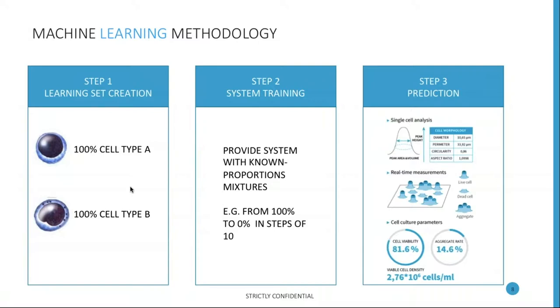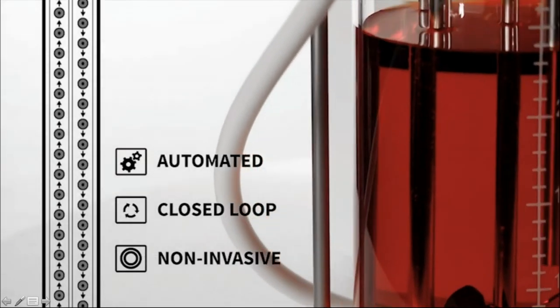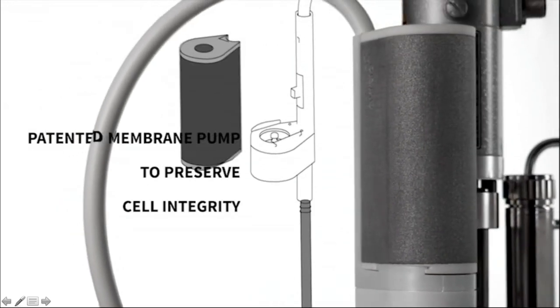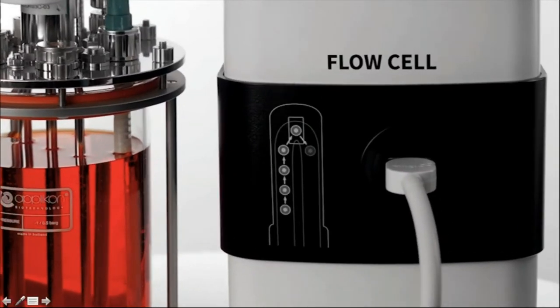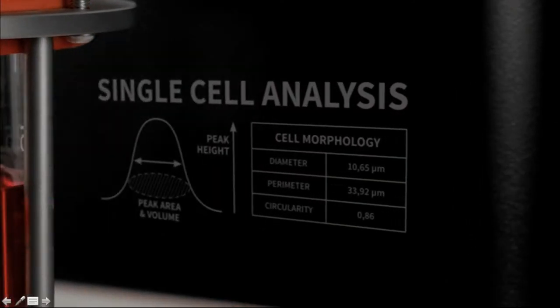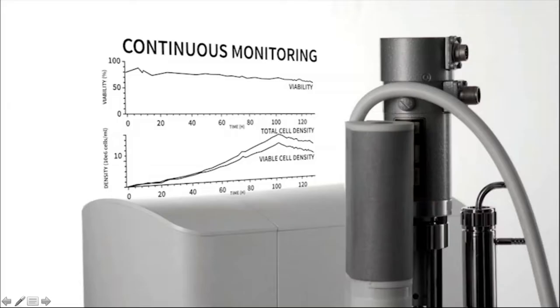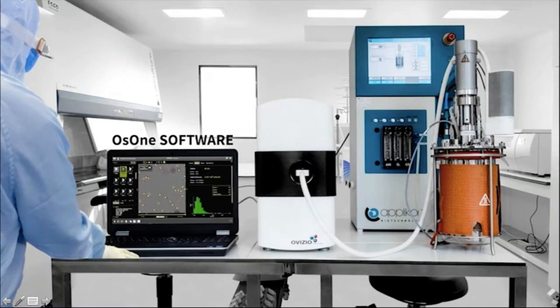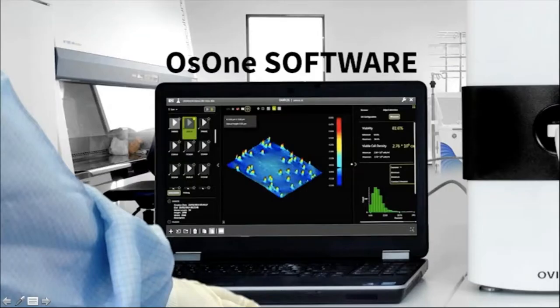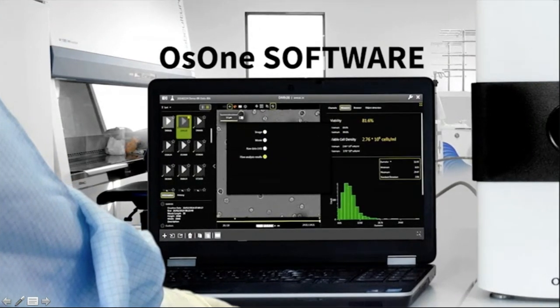The device we use for that is the I-Line F, an inline microscope that comes with a single-use BioConnect — a single-use sampling probe attached to the bioreactor. It can work with different types of bioreactors and creates a loop of cells via a pump that are pumped to the microscope. It's a closed-loop system with no risk of contamination, and images are analyzed in real time on the computer next to the microscope.